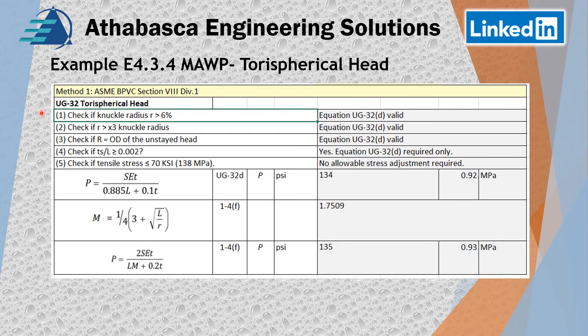Now we've organized our spreadsheet and I've taken five checks. First, I check whether the knuckle radius is greater than 6% — pass. Second, I check whether R is greater than three times the knuckle radius — check. Third, I check where R is equal to the OD for an unstayed head — done. Fourth, we check whether t/L is greater than 0.002 — yes. So we use that equation. Fifth, we check tensile strength less than 70 KSI — no adjustment required, as discussed.